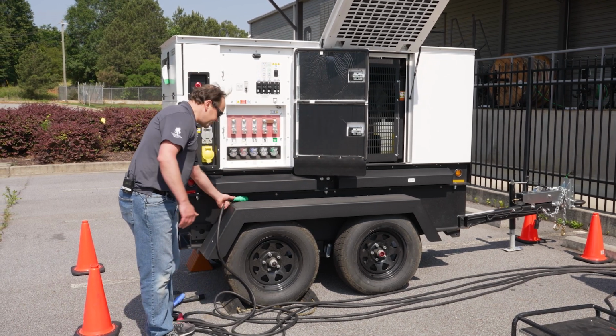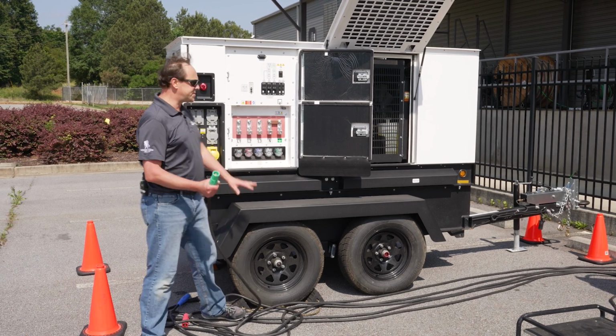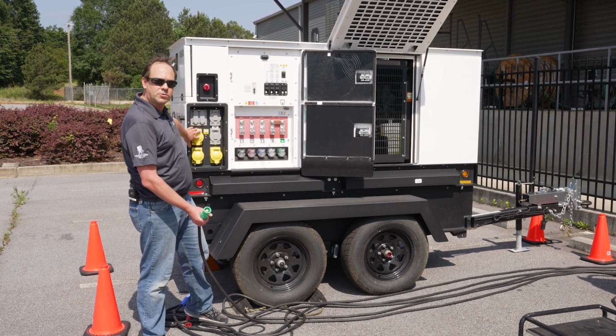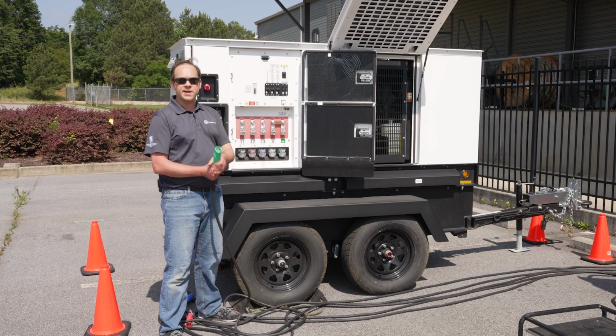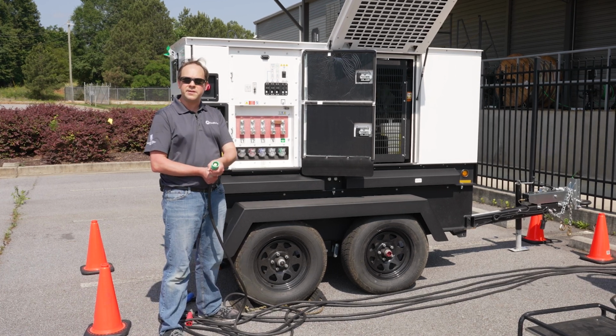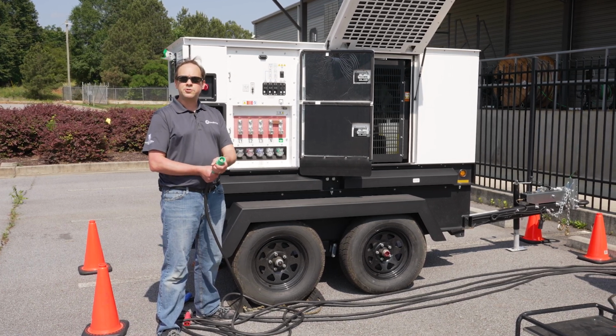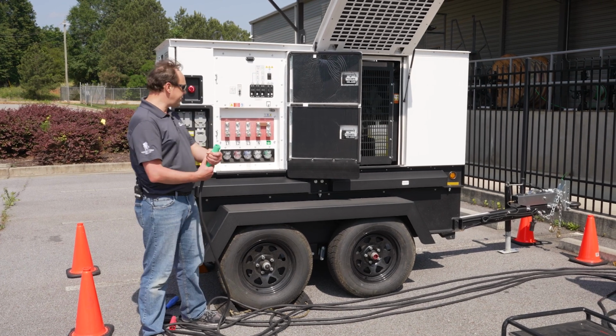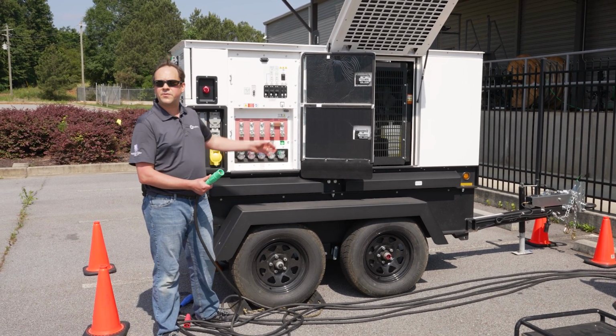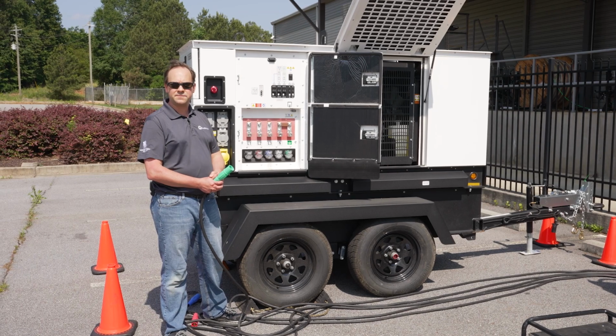Now, cam lock connectors are single pole devices versus these multi-pole devices where everything is in one jacket. In a single pole device, I have one connection point from end to end that's usually either for ground, neutral, or any of the hots. Now, when I connect them, I'm going to connect my ground first, followed by my neutral and my three legs.